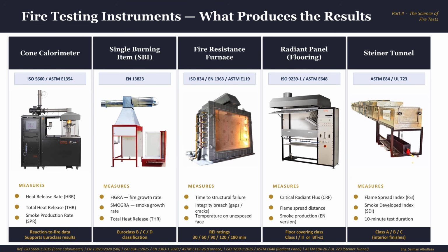Remember the R, E, and I that we mentioned before? These things are monitored together here: resistance load, integrity load, and insulation load. The clock runs until one of them fails. The time recorded at that point, that's your rating, 30, 90, 120, or maybe 180. What comes out is the exact duration of the element that was proven. 30 minutes fire rated door, 2 hours fire rated walls. That's it, exactly as it is.